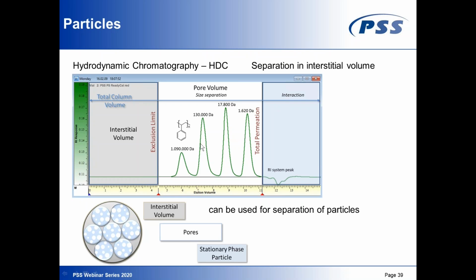This is how we show how a separation on a typical GPC SEC column occurs. We have here in blue our particles, in white our pores, and in gray our interstitial volume. Interstitial volume means that before the exclusion limit, nothing can elute. Then we have the typical GPC SEC separation, which takes place in the white pores. We have a separation range from around 4.5 to 12 milliliters, so around 6 to 7 milliliters, where we can eventually separate according to size. What if we do not separate in the pores, but in the interstitial volume? We can also have a separation there. And this, for example, can be used for particles.